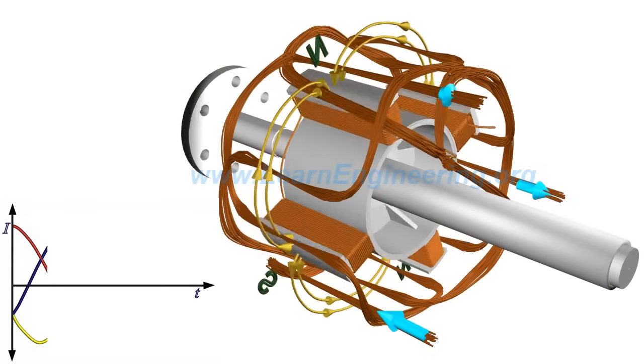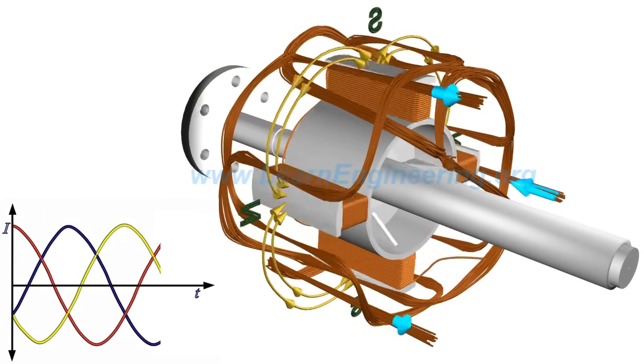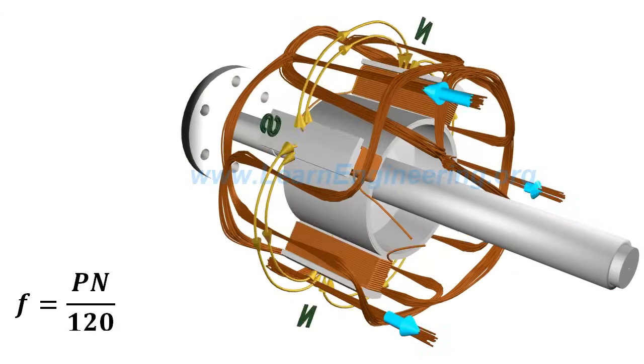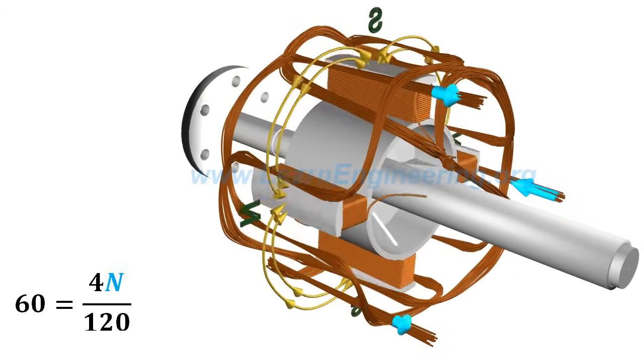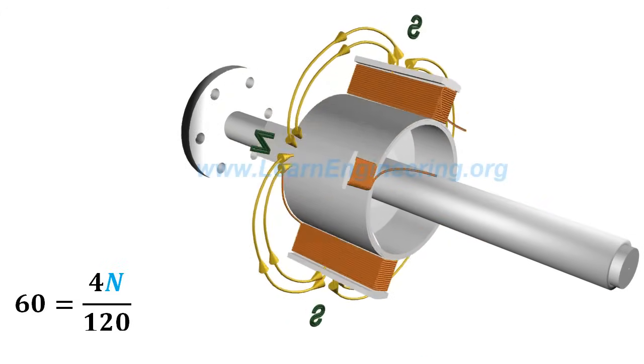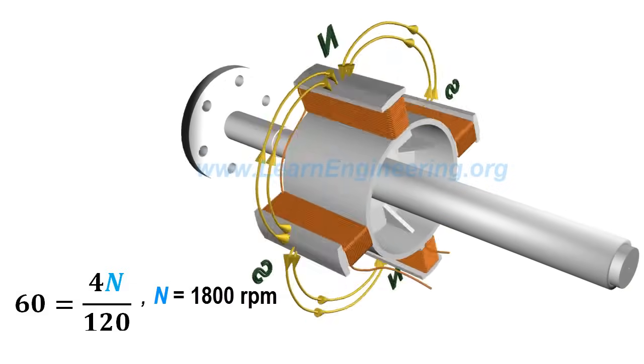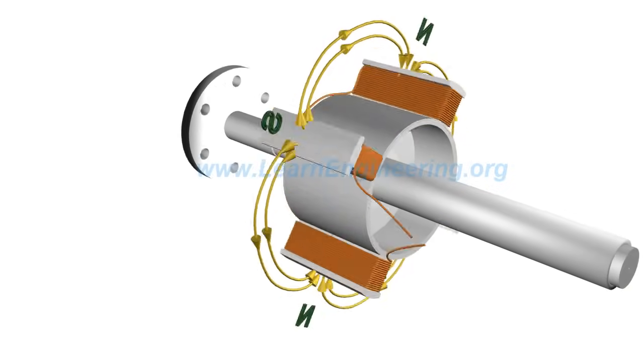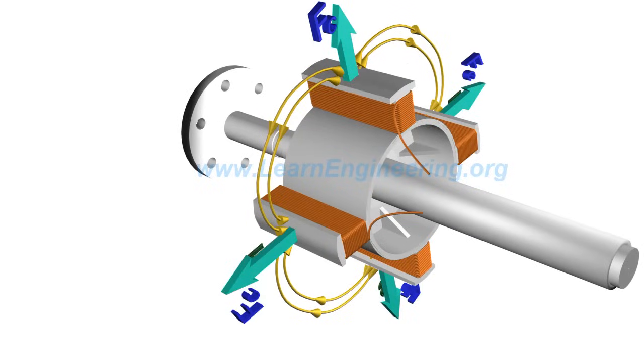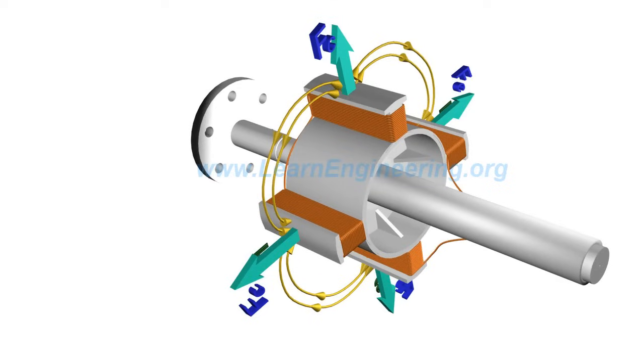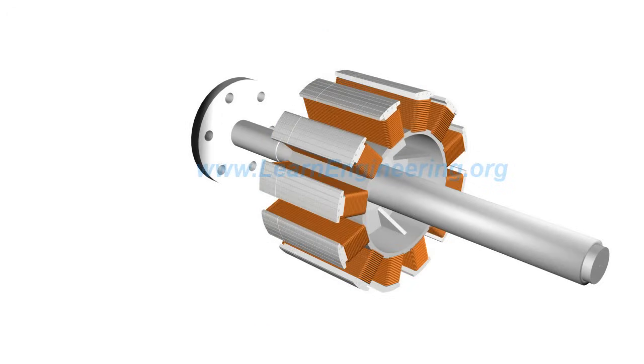It is clear from this equation that in order to produce 60 Hz electricity, a four-pole rotor should run at a very high RPM. Such high RPM would induce a tremendous centrifugal force on the poles of the rotor, and it may fail mechanically over time. So, salient pole rotors generally have 10 to 20 poles, which demands lower RPM.